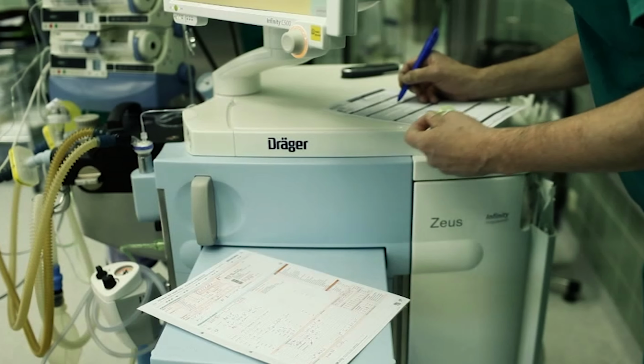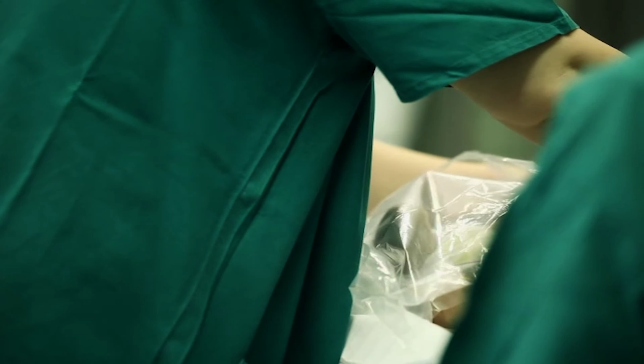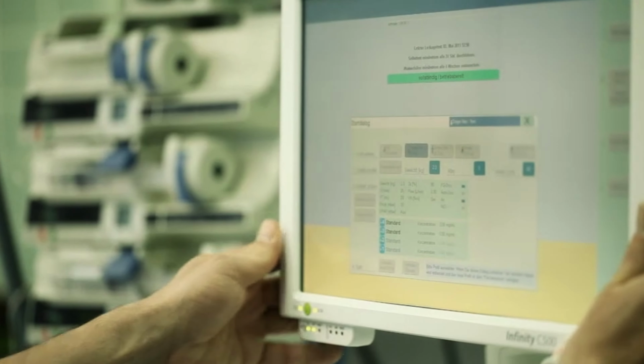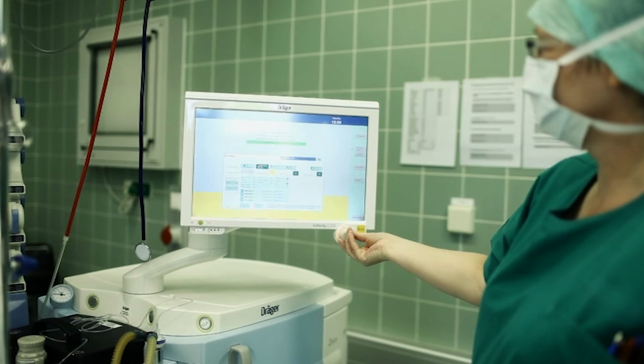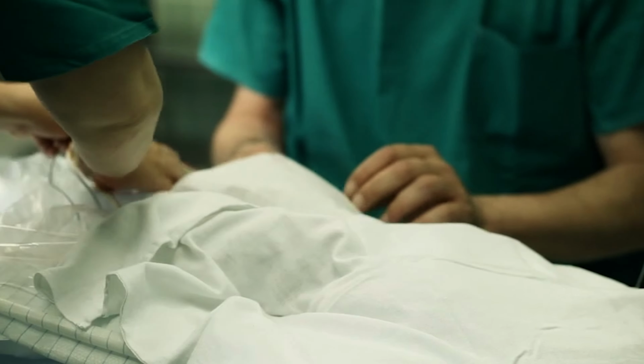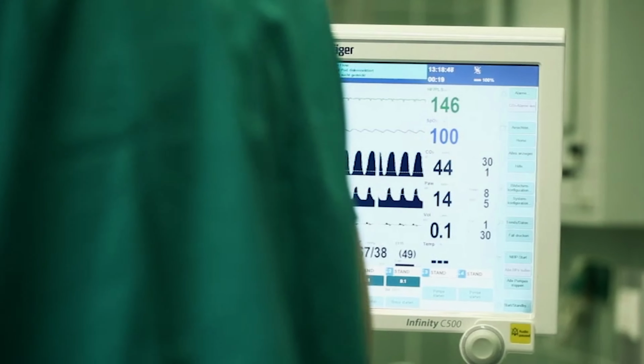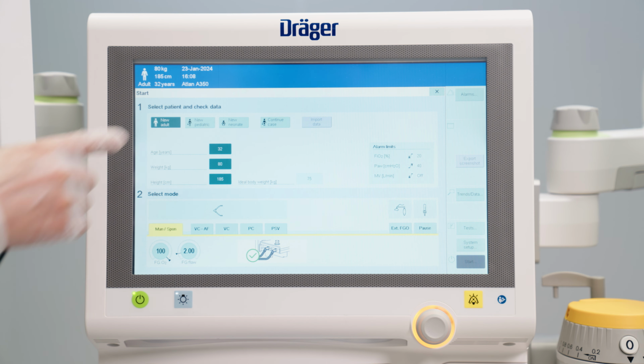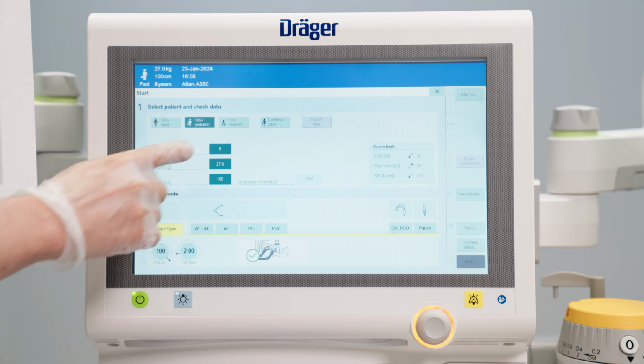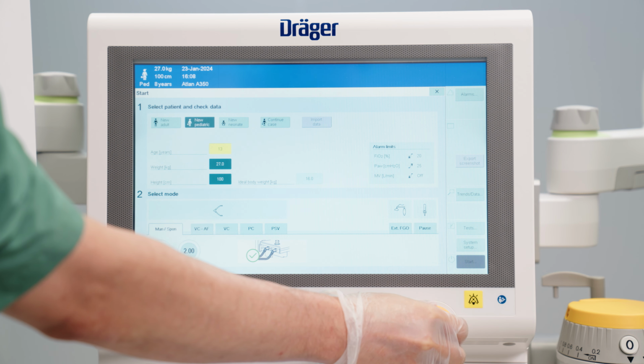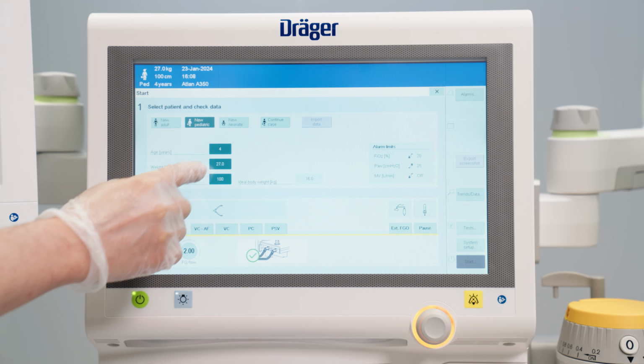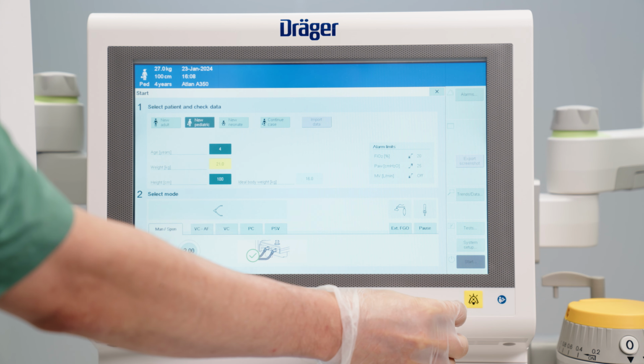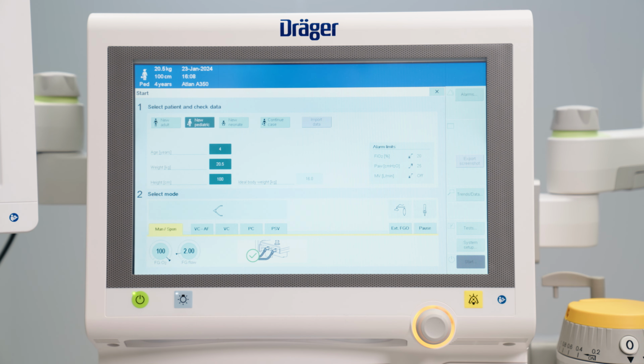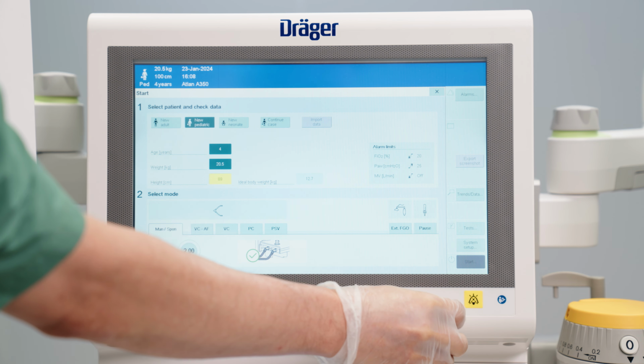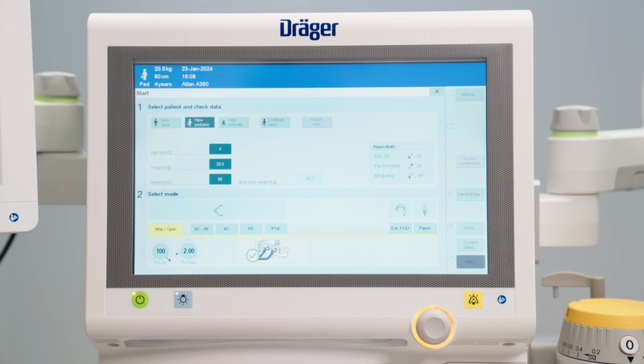Preparing the anesthesia workplace is of utmost importance. Once the small patient is induced, the time for oxygen desaturation can be as short as 90 seconds. Therefore, a swift change by the device to appropriate mechanical ventilation is essential. Atlan family anesthesia machines facilitate this by offering customized pre-setting for all patient categories, including pediatric patients and neonates. After selecting the patient category, relevant settings and alarms will adapt automatically, with only few manual adaptations needed when necessary.